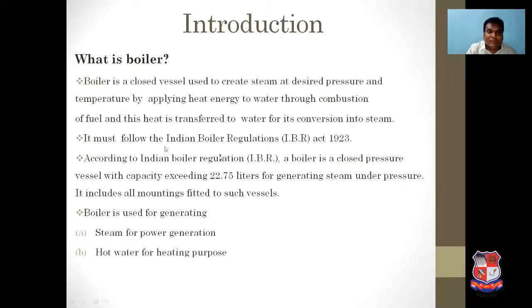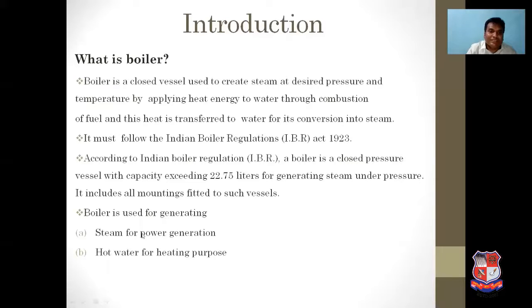According to the Indian Boiler Regulation, a boiler is a closed pressure vessel with a capacity exceeding 22.75 liters for generating steam under pressure. This kind of boiler must have mountings fitted, which are necessary for the safety of the boiler. A boiler is utilized for generating steam for power generation and hot water for heating purposes.